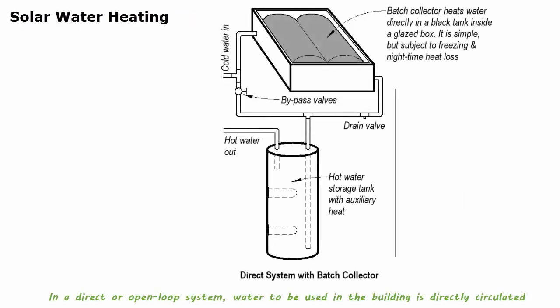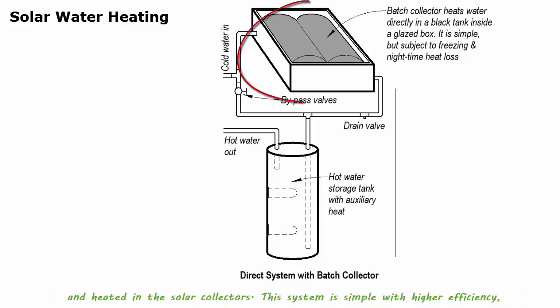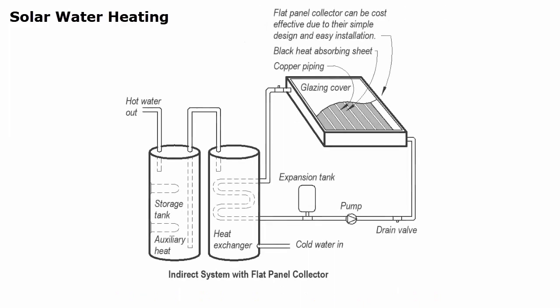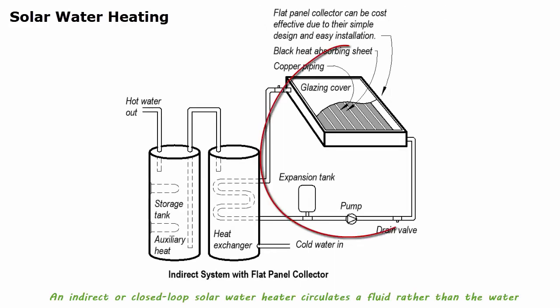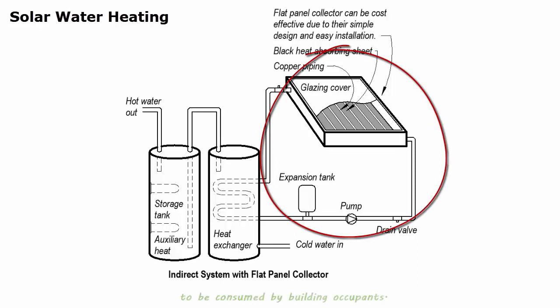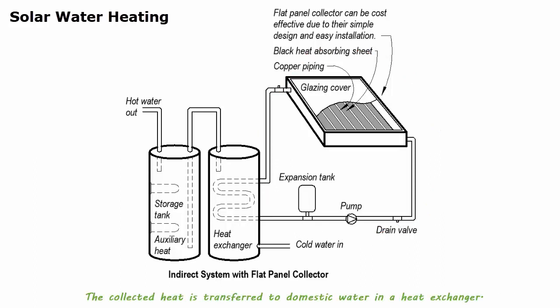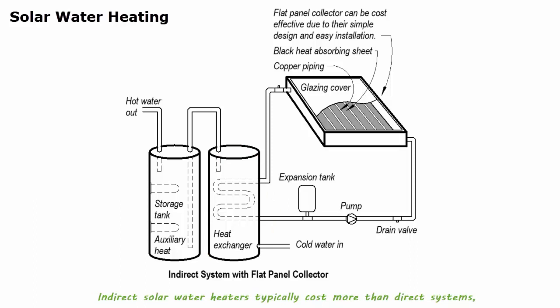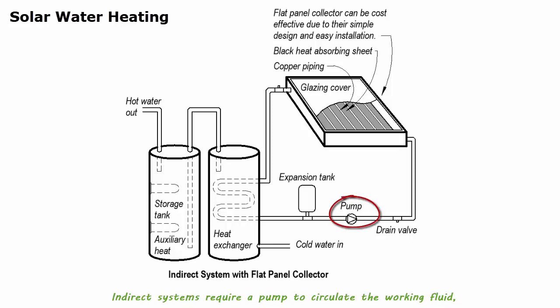In a direct or open loop system, water to be used in the building is directly circulated and heated in the solar collectors. This system is simple with higher efficiency, but water is subject to freezing and potential contamination. An indirect or closed loop solar water heater circulates a fluid rather than the water to be consumed by building occupants; the collected heat is transferred to domestic water in a heat exchanger. Indirect solar water heaters typically cost more than direct systems but are more resistant to freezing, making them popular in colder climates. Indirect systems require a pump to circulate the working fluid, which consumes energy and needs maintenance.